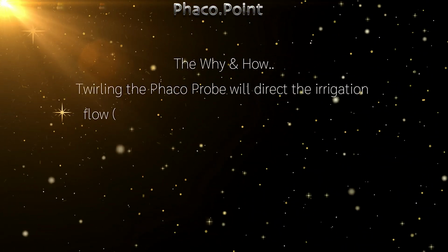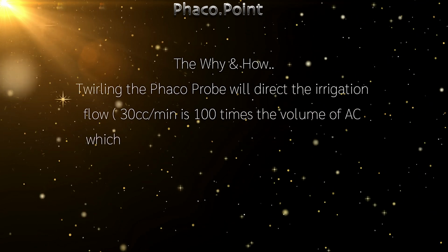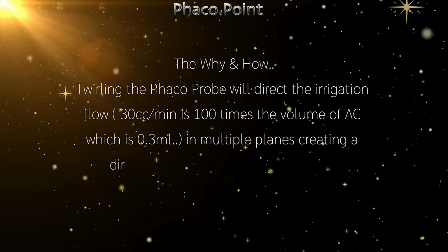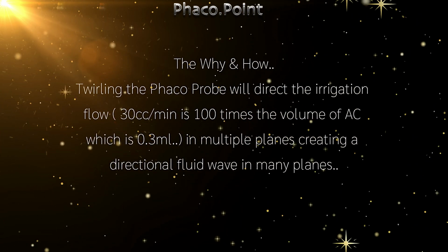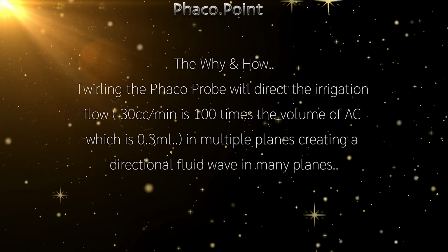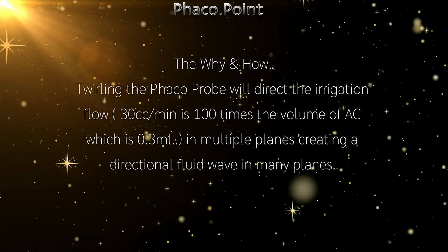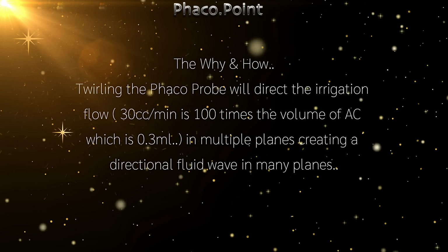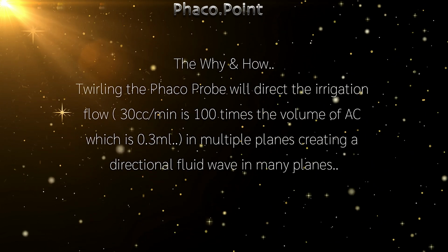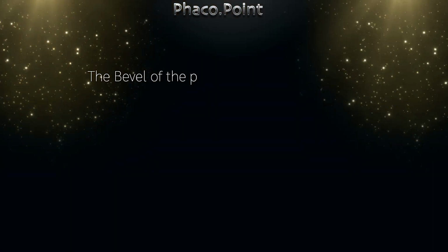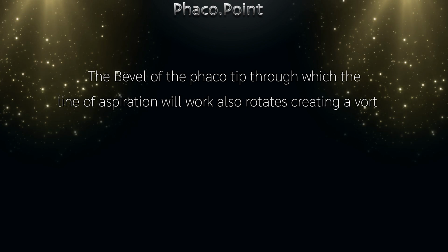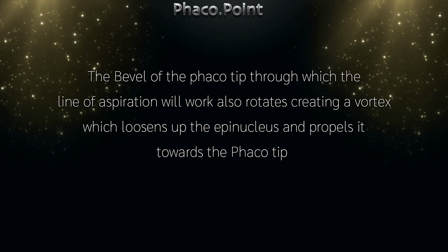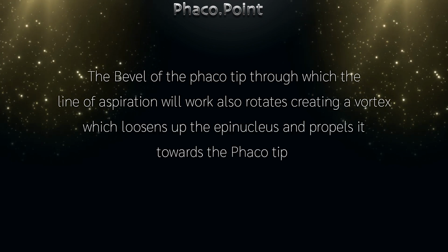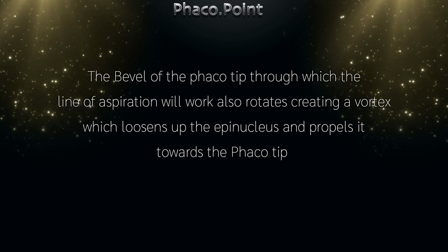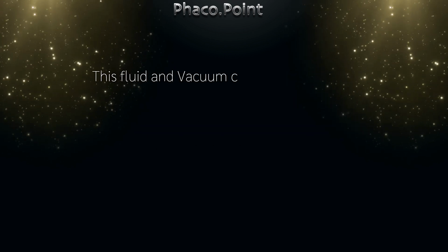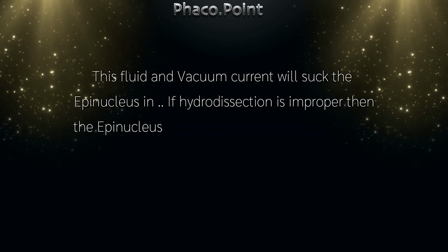Now, when you twirl the phaco probe, this will direct the irrigation flow. We're talking about 30 cc per minute, which is 100 times the volume of the anterior chamber, which is usually about 0.3 ml. This fluid flow will occur in multiple planes, creating a directional fluid wave in many planes within the eye. The bevel of the phaco tip through which the line of aspiration will work also rotates, creating a vortex. This loosens up the epinucleus and propels it towards the phaco tip. The fluid as well as the vacuum current will suck the epinucleus in.